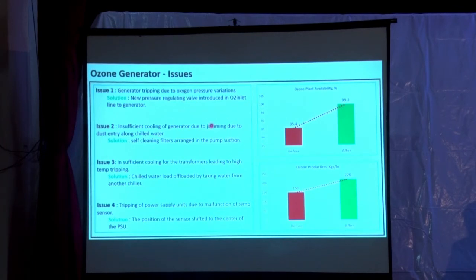From the start, we have faced various challenges like ozone generator tripping because of inlet oxygen pressure variations. For that, we have provided a regulating system for the pressure with a vent valve. From the oxygen plant also we maintain the pressure, as well as at the ozone generator inlet we maintain a pressure control system. That has eliminated the pressure fluctuations. There was also insufficient cooling water because of jamming in the system from dust entry. For that, we have provided self-cleaning filters.